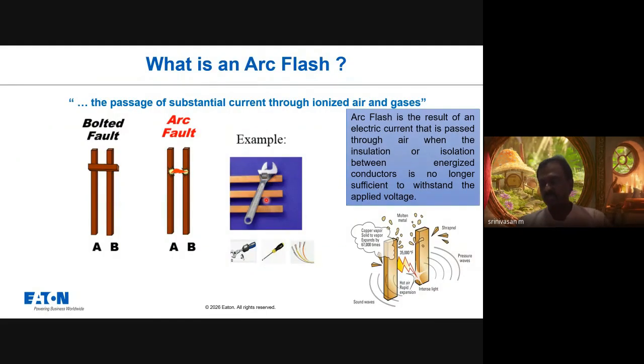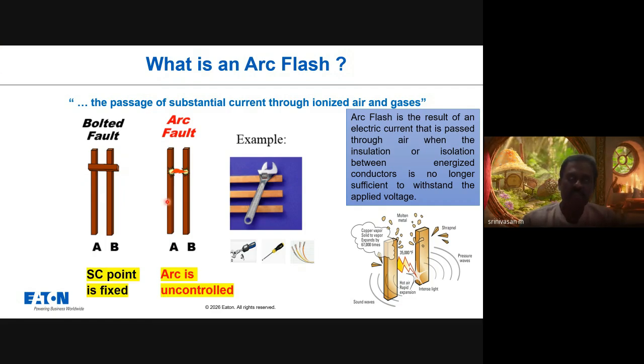Before jumping to Arcon, the arc mitigation device, we'll talk about what is meant by arc flash. You might have seen in the single line diagram that we indicate electrical terms like ICW, 50 kA for 1 second or 50 kA for 3 seconds. So we fix the bolted short at one location. That means the short circuit point is fixed and immovable in general. But this is nothing but a low impedance short circuit.